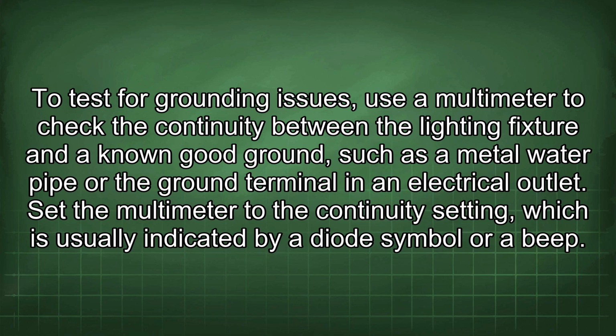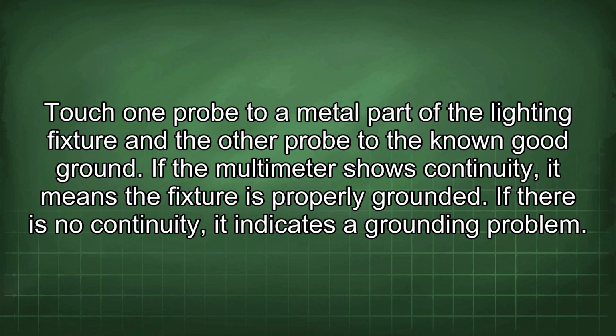To test for grounding issues, use a multimeter to check the continuity between a lighting fixture and a known good ground, such as a metal water pipe or the ground terminal in an electrical outlet. Set the multimeter to the continuity setting, which is usually indicated by a diode symbol or a beep. Touch one probe to a metal part of the lighting fixture and the other probe to the known good ground. If the multimeter shows continuity, it means the fixture is properly grounded. If there is no continuity, it indicates a grounding problem.